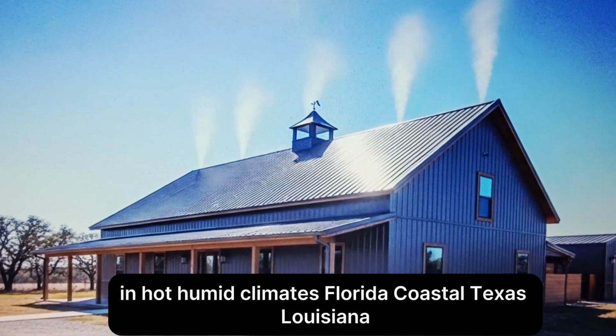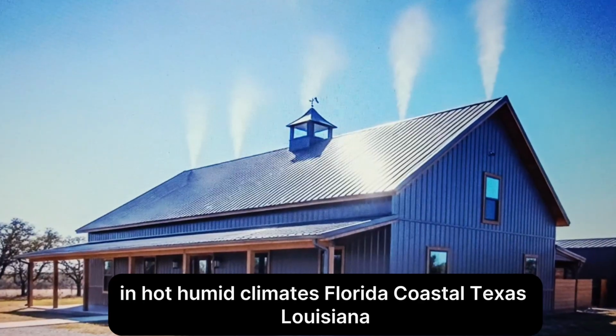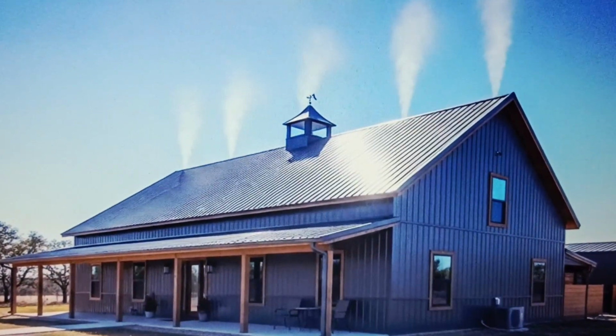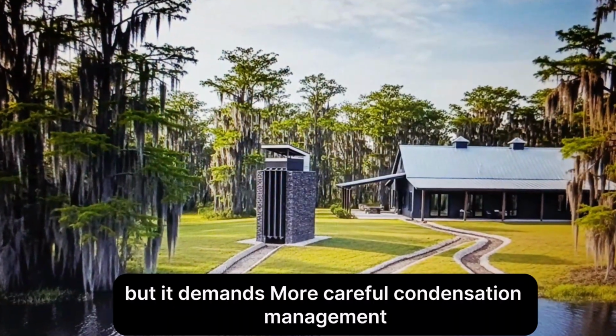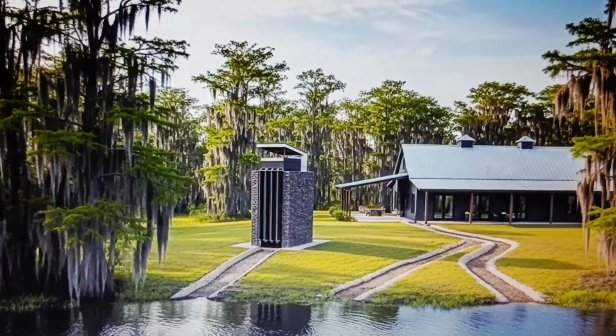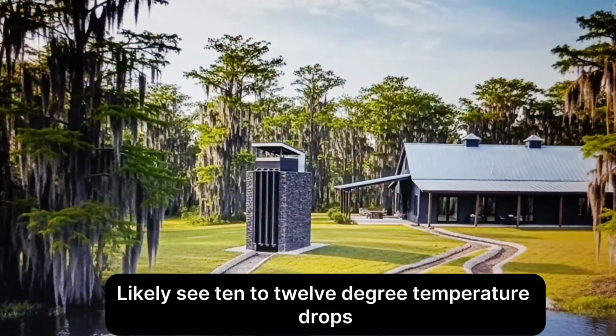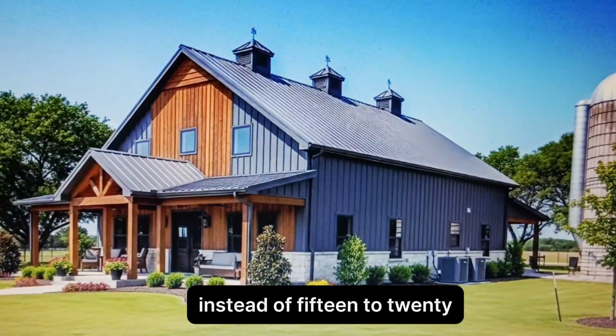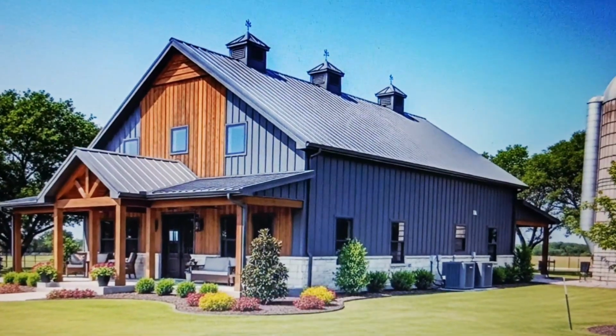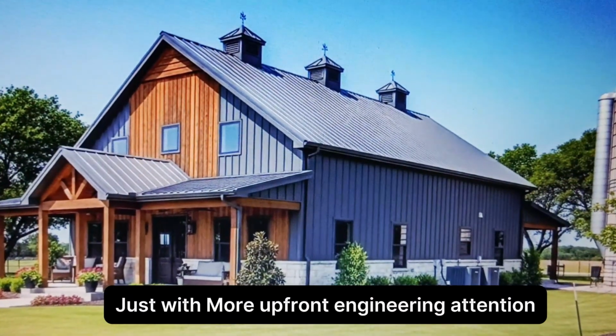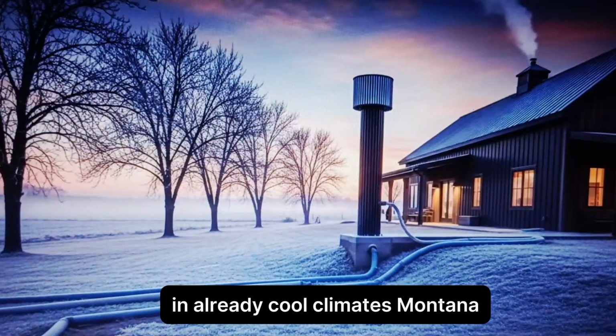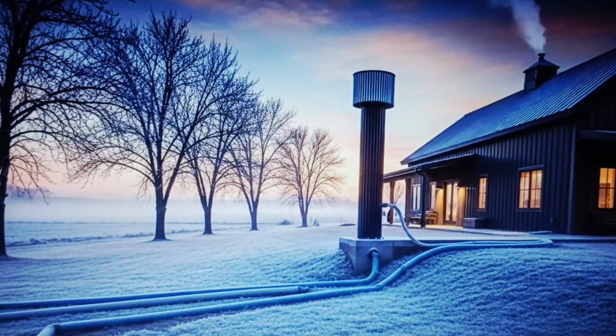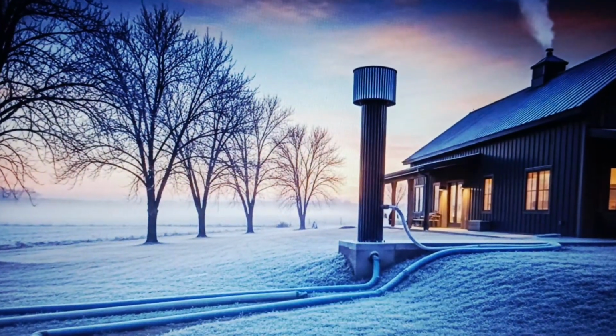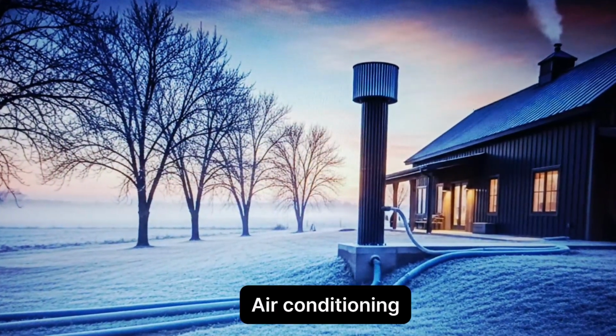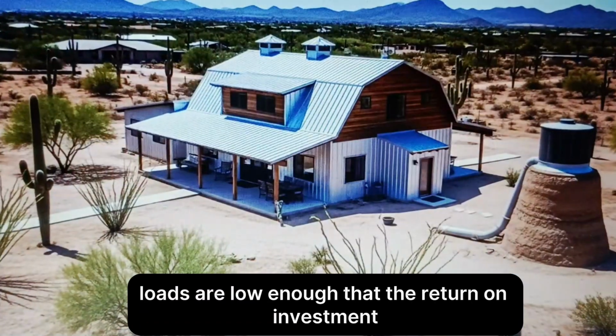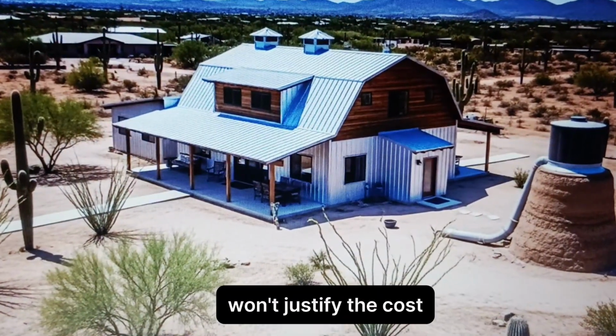In hot, humid climates, Florida, coastal Texas, Louisiana, the system still works, but it demands more careful condensation management. You'll likely see 10 to 12 degree temperature drops instead of 15 to 20. Still significant. Still worth doing. Just with more upfront engineering attention. In already cool climates, Montana, Maine, the Pacific Northwest, you probably don't need this. Air conditioning loads are low enough that the return on investment won't justify the cost.